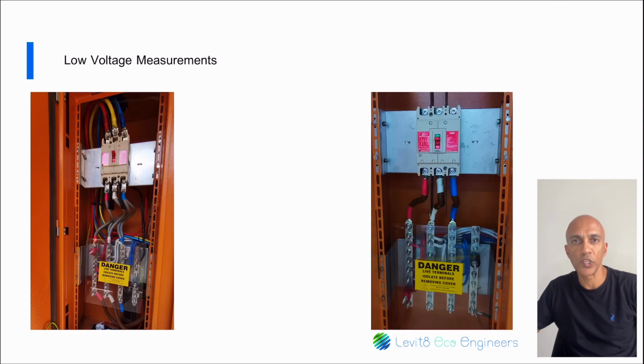If you are measuring the total load at the main incoming supply, take careful note of this scenario and ensure that you measure on the bus bars directly below the main circuit breaker or above the main circuit breaker, and not anywhere where the various feeder wires connect to the bus bar. If you measure below the feeder offtakes, some of the current may have already split from the bus bar.